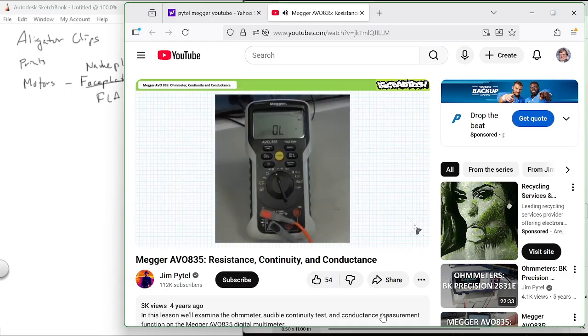To place the AVO 835 into audible continuity test mode, press the yellow mode button in the center while in ohm meter mode. When the probes are separated, the DMM is silent. When I touch the probes together, the DMM produces an audible tone. The audible continuity test mode is pretty handy because you can check continuity of a mess of wires without ever having to glance up and look at the screen and interpret numbers.